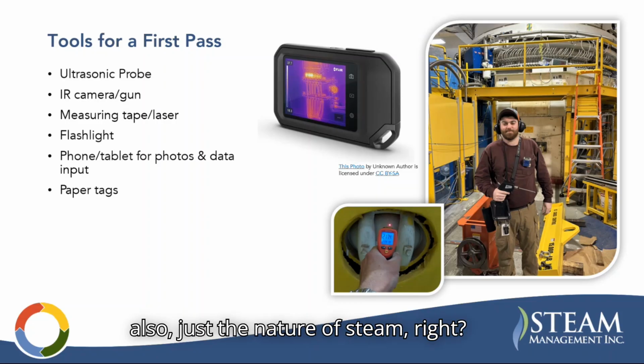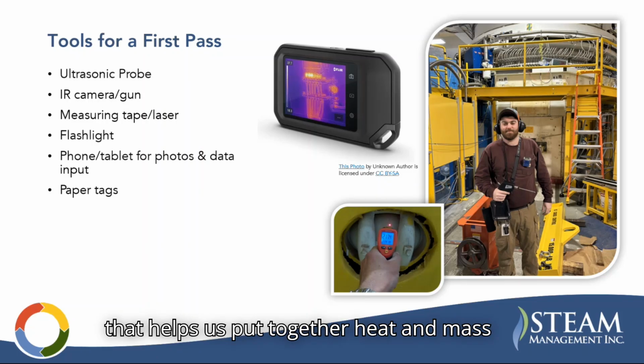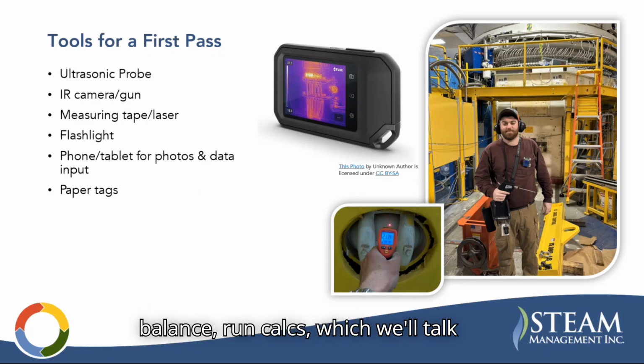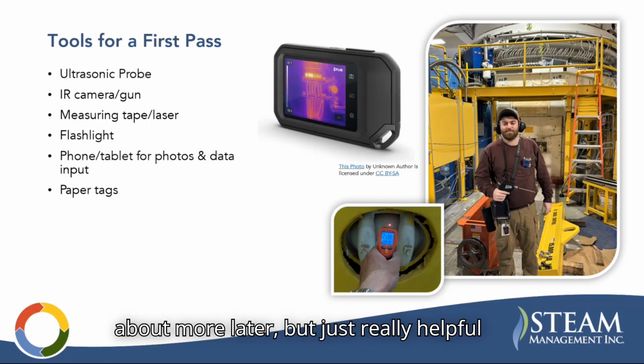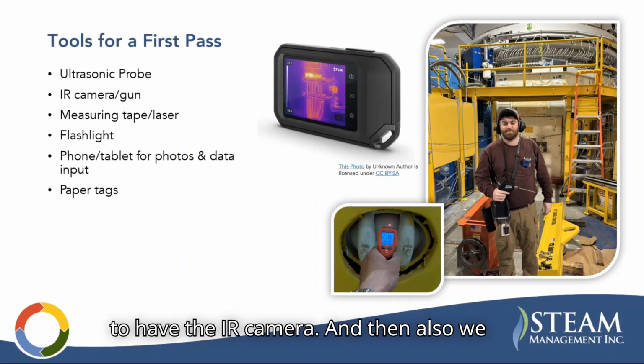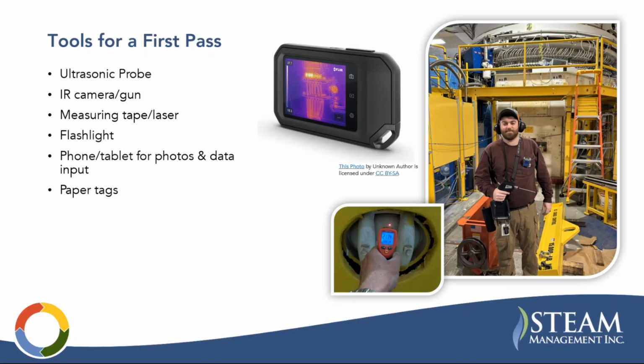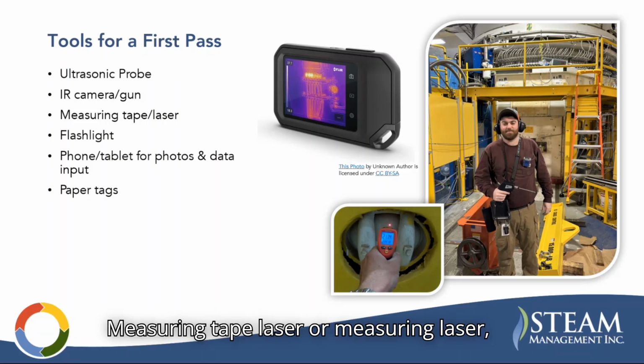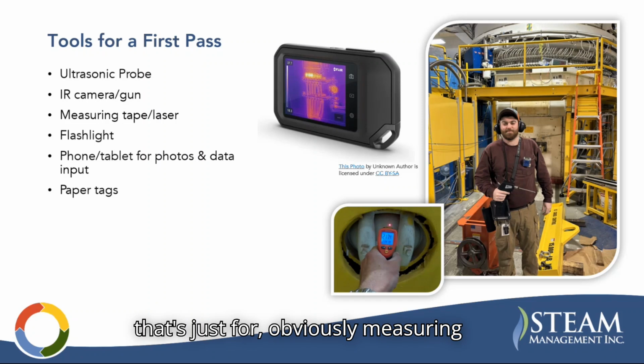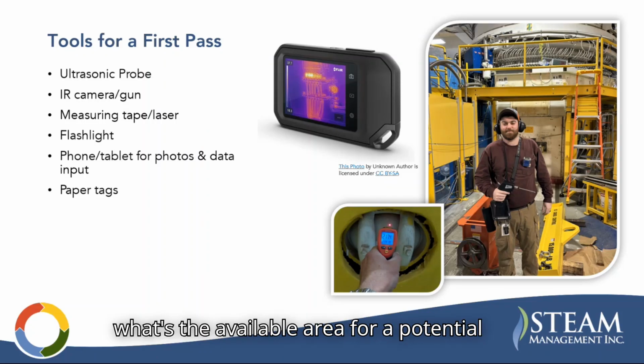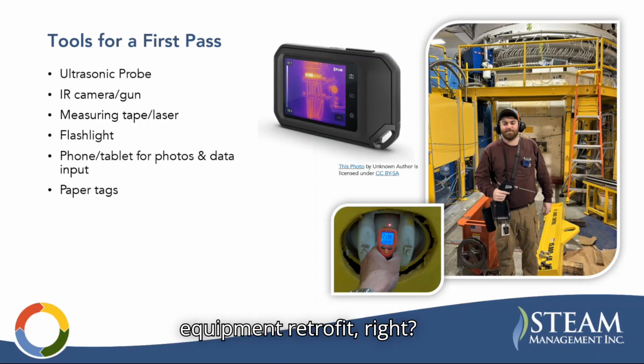You also have the nature of steam, right? If you know the temperature of a line, you know all the other properties of the steam. So that helps us put together a heat and mass balance and run calcs, which we'll talk about more later, but it's just really helpful to have the IR camera. And then we also use that as a backup test for steam trap testing, which we'll talk about as well. Measuring tape or measuring laser, that's obviously for measuring lengths of insulation if there's missing insulation, or what's the available area for a potential equipment retrofit, right?